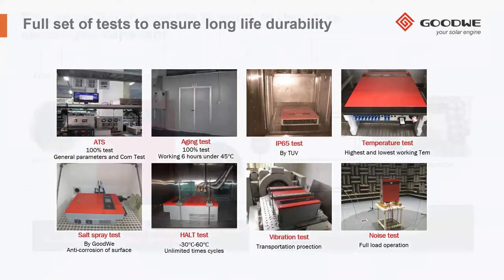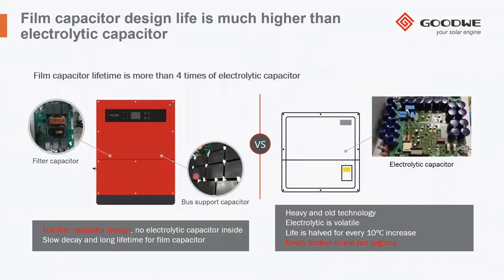But we also have some features which normally you cannot appreciate without opening the inverter. That's why we show this picture. As an example, we have a thin film capacitor instead of a standard capacitor, and this ensures 4 times longer life with respect to an electrolytic capacitor. So it's a small detail in the electrical project, but just to give you an example of the good quality of the product that we use, and also of the smartness of the electrical project that we made to set up the MT inverter.